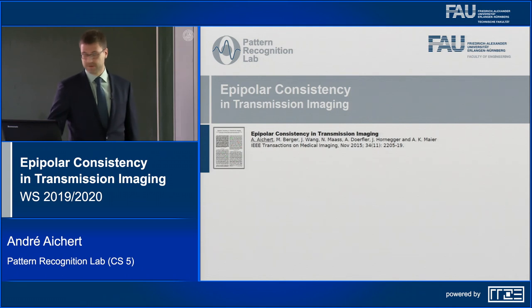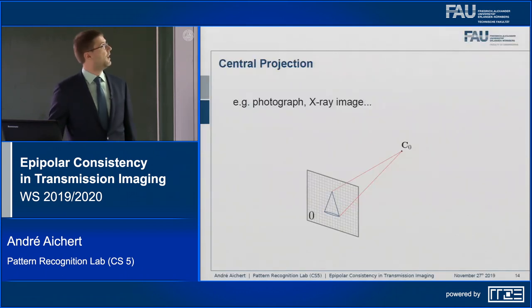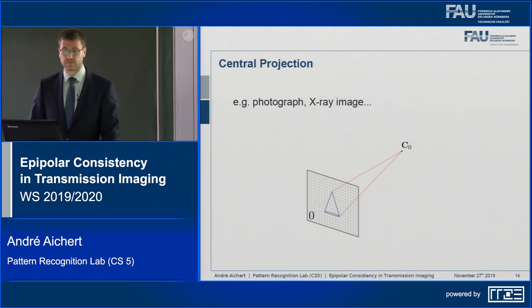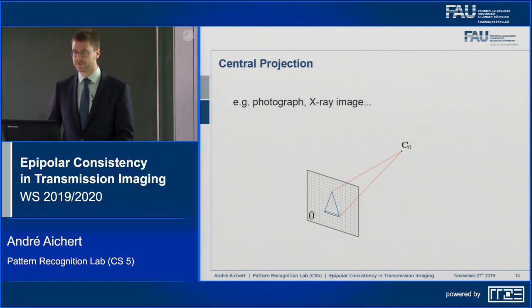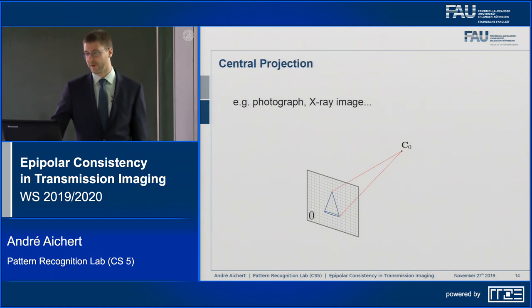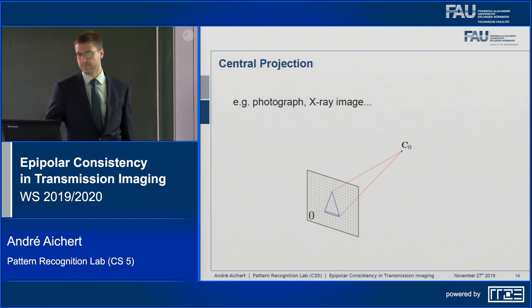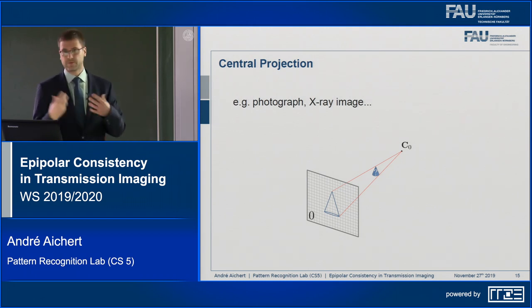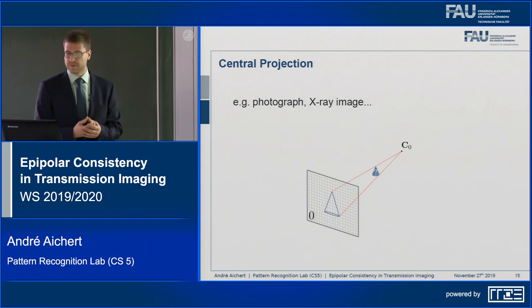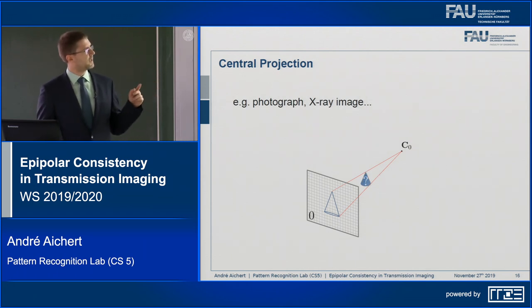Starting with prerequisites — specifically epipolar geometry. Projection for a flat-panel detector x-ray system is basically the same as in a photograph: you have an x-ray source which is like the camera center, and a flat-panel detector which serves as the image plane where x-rays are detected. If you can see a conical shape on the detector, that is because a 3D object in the ray path attenuates some of the radiation — you can think of it as a shadow image.